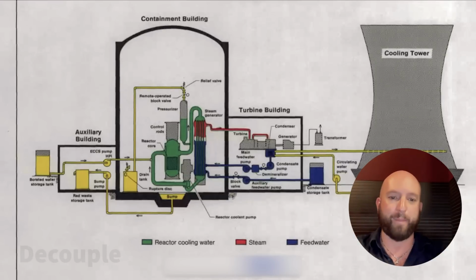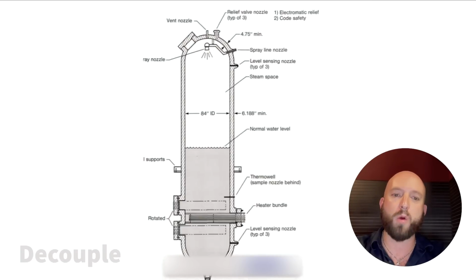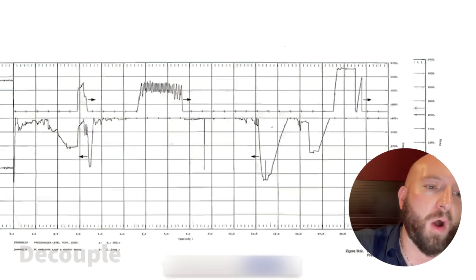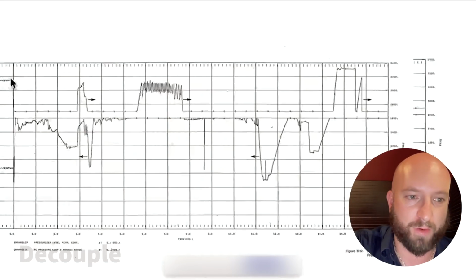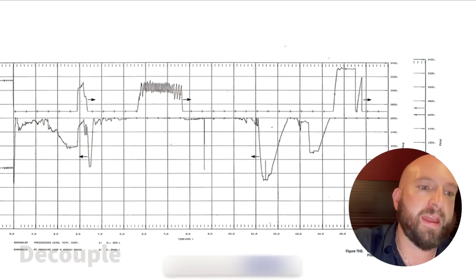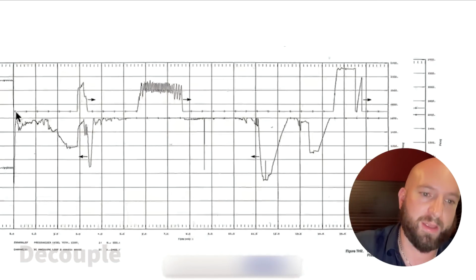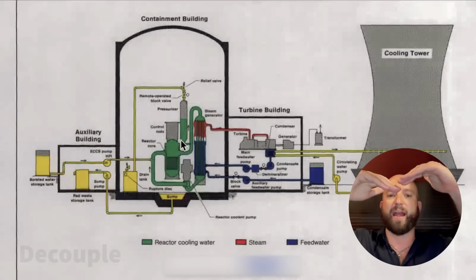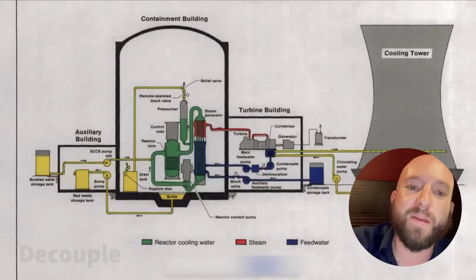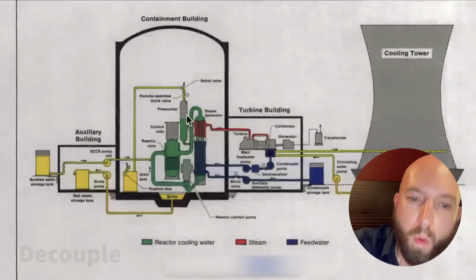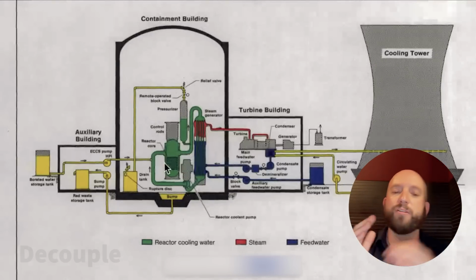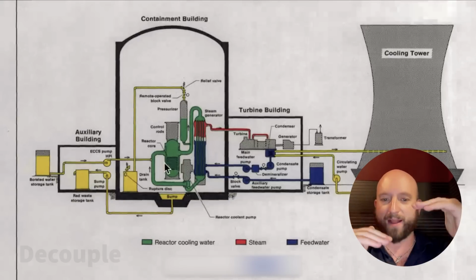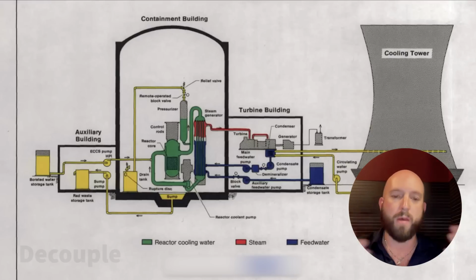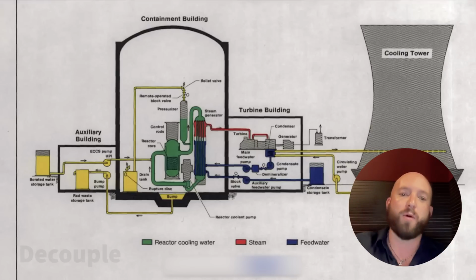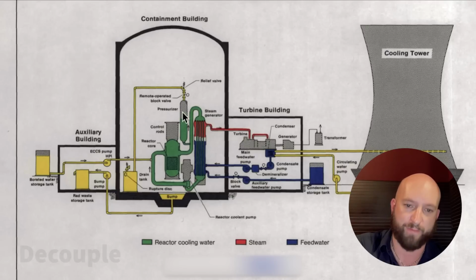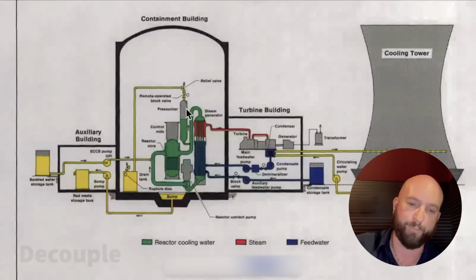And then something else starts happening that is very strange, and this is actually from the actual plant. Although the reactor coolant system pressure, which is this line over here, dropped a lot, the level in the pressurizer is surging. The pressurizer is at the highest point in the reactor coolant system, and it is the main way that they measure the level of water in the reactor coolant system. So what does this mean? They don't have a way to directly measure the amount of water in the reactor pressure vessel, because that's always assumed to be full of water. So the operators look to this pressurizer level to figure out how much water is in the system. And that makes a lot of sense.